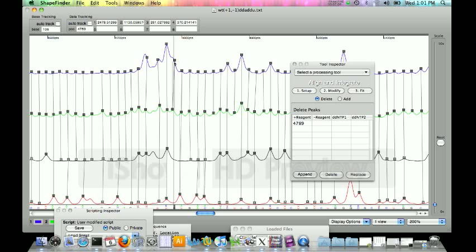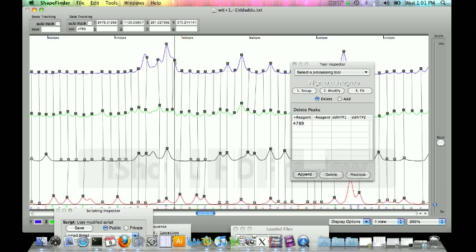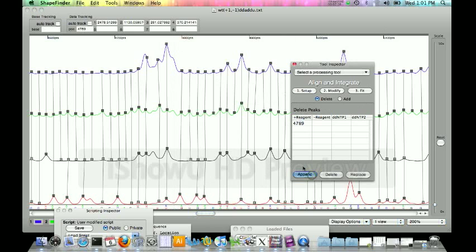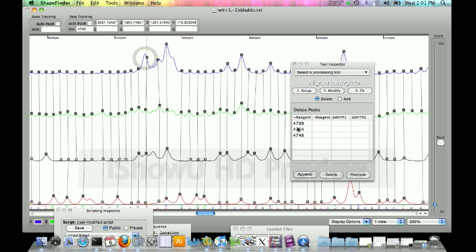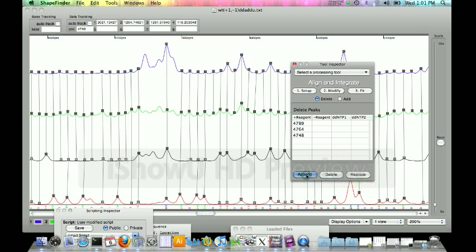Anytime there's a peak in the first filter it will usually tie it to a peak in the second filter. This peak in the second filter won't appear if you don't have a peak in the first filter. Again we just click on our first peak in our first filter, go ahead and click delete, it gets rid of the whole thing, no problem. You can also delete more than one peak at a time. We're going to click on the other two boxes that we want to delete here, add them to the list, and delete.